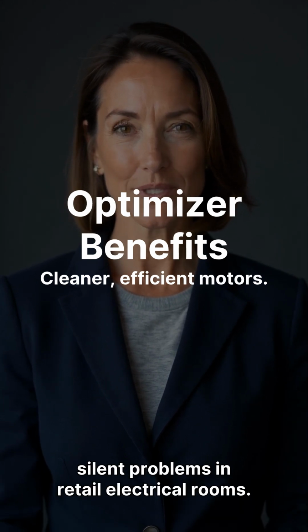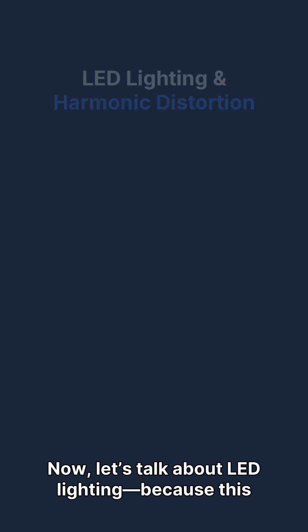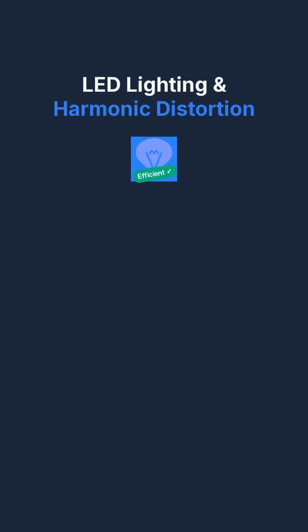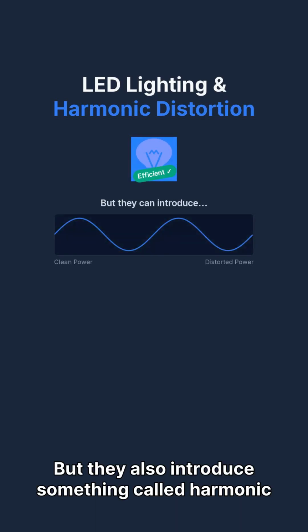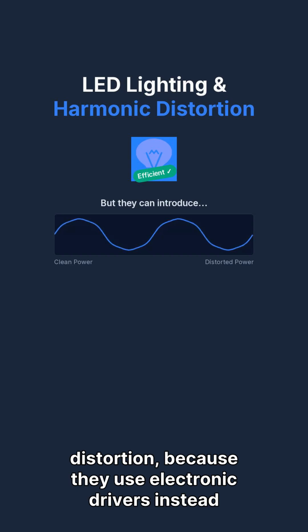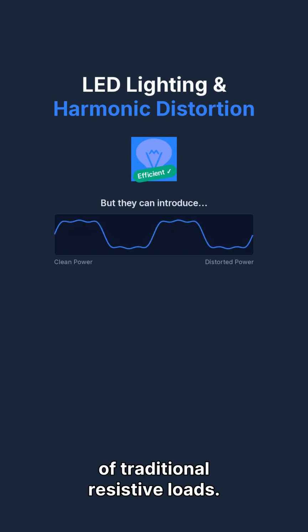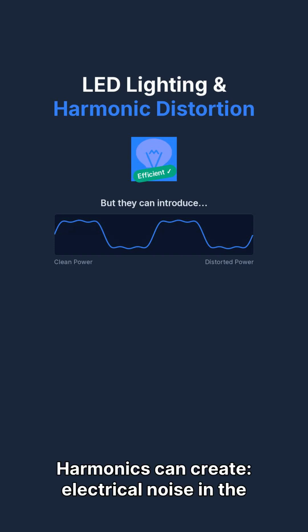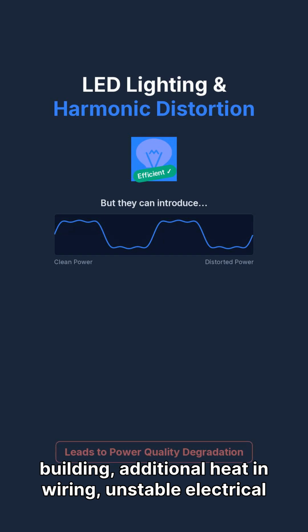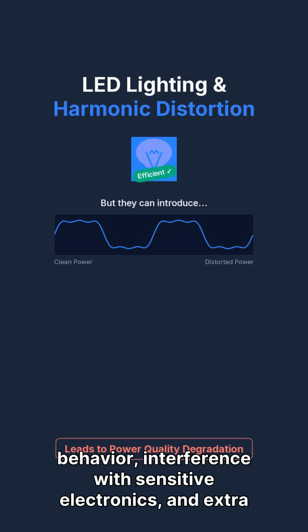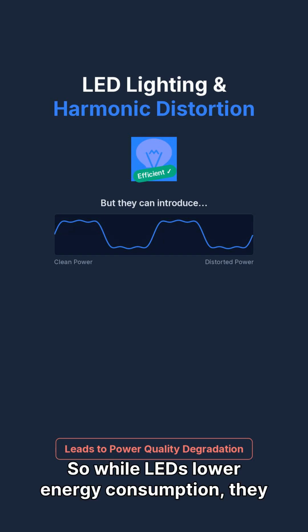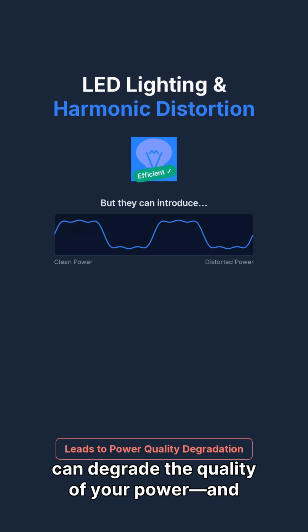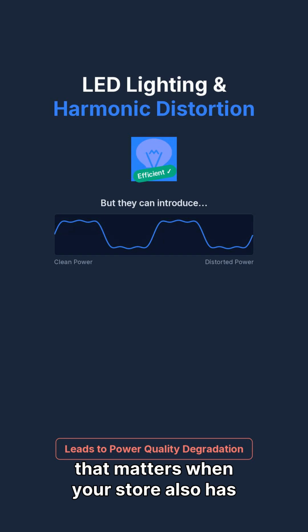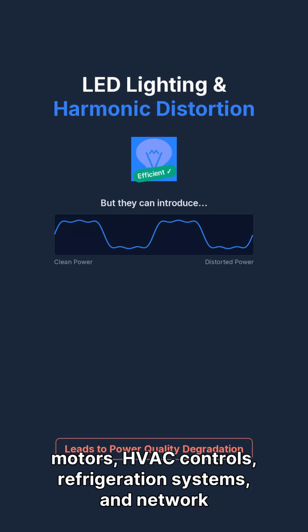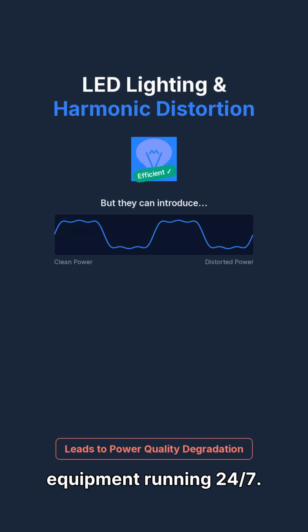Now, let's talk about LED lighting, because this surprises a lot of store owners. LEDs are efficient, yes, but they also introduce something called harmonic distortion, because they use electronic drivers instead of traditional resistive loads. Harmonics can create electrical noise in the building, additional heat in wiring, unstable electrical behavior, interference with sensitive electronics, and extra load on your distribution system. So while LEDs lower energy consumption, they can degrade the quality of your power, and that matters when your store also has motors, HVAC controls, refrigeration systems, and network equipment running 24/7.